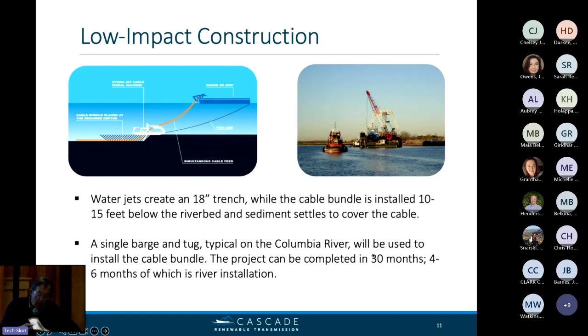The picture on the left shows what we call a hydroplow, also called a lay burial device, and the picture on the right shows basically what we have. It requires a barge and a couple of tugboats, with the cable loaded onto the barge. Using the same feed mechanism shown earlier, it comes down off the barge in catenary, then goes into the hydroplow, into the stinger.